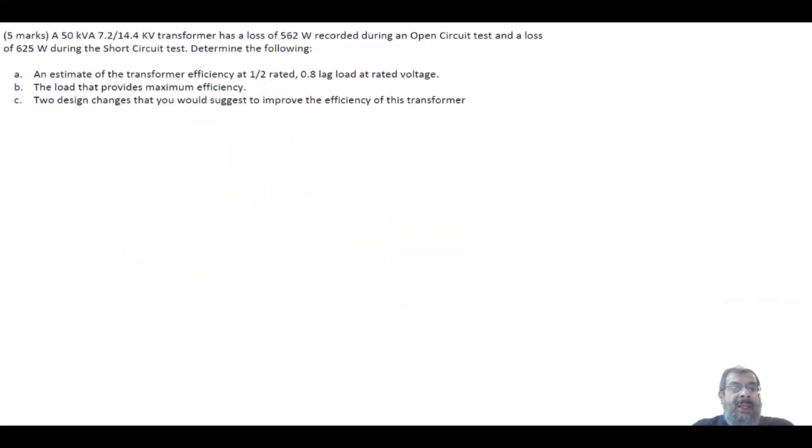The last part, two design changes that you would suggest to improve the efficiency. Now, we know that the efficiency is equal to Pout over Pout plus summation of the losses. And we have two losses. We have the winding loss, which is equal to I squared R. Now, I you don't have control over, because this is the demand coming from the customer. So you have control over R. What is R? It's the resistance of the winding.